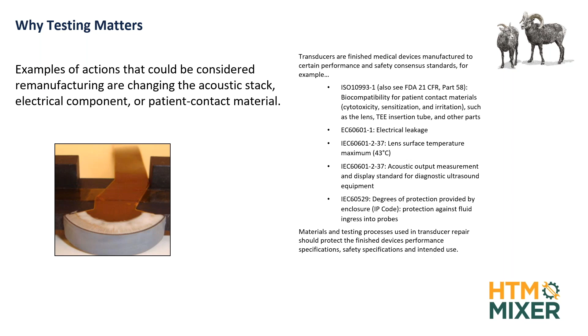So here it is. So the lens, here's the transducer. The FDA will tell you in the guidance document what standards apply for that particular device. Okay. And all of you have heard of those standards, right? The IEC standards, etc., because you're doing electrical leakage testing on all kinds of stuff in the hospital and everything. So the lens material is subject to all of these. The housing material, these. And the cable, again, different ones. There are also fluid ingress requirements: how deep can you put the probe into fluid for cleaning, etc., so that you don't allow fluid ingress.